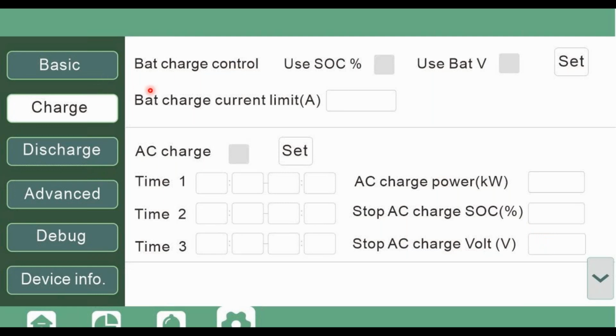So here we stipulate the recommended battery charge current limit. If we have 3 E-flexes, then you put 150. If you have 1 Evo Max, then you stipulate 180, right? Obviously, this goes from 167 on the 8K, it goes to 210 on the 10K, and it goes to 250 on the 12K. Okay. If you wanted to enable AC charge, you can do so.